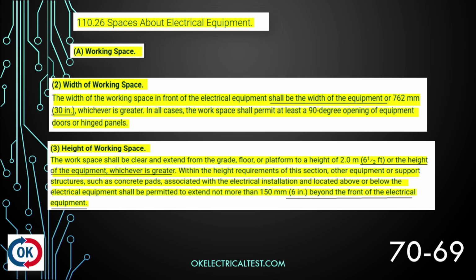Now number 3, the height of the working space. It says the workspace shall be clear and extend from the grade, floor, or platform to a height of 6.5 feet or the height of the equipment, whichever is greater. Again, our minimum is going to be 6.5 feet, but if I've got an 8-foot tall piece of equipment, the height of my working space in front of that electrical equipment is going to be 8 feet. Just as a clarification, this is where we have electrical parts that need to be serviced while energized. That's under letter A, working space. It's where equipment is likely to require service while energized that these width, height, and depth requirements come into play.